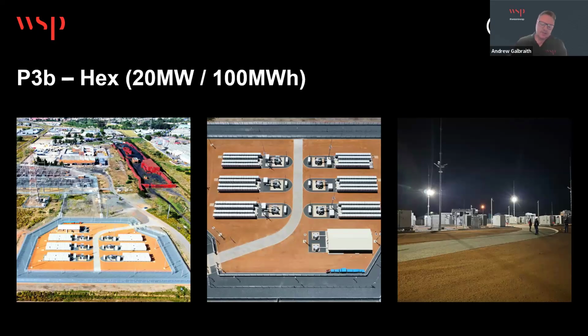Okay, the final one was part of package 3B. This was a separate contractor down in the Western Cape, near Worcester. The site's called Hex. It was a 20 megawatt, 100 megawatt hour battery. As you can see, the autonomy is 5 hours as opposed to 4 on the other two sites.